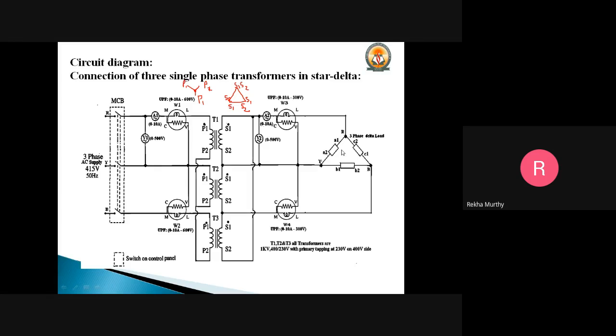For each step we have to take down the readings of all the meters and continue that loading until the transformer supplies the rated power of the respective configuration. Okay, that is how we have to vary this load and note down the readings. Tabulate the columns: primary voltage, primary current, secondary voltage, secondary current, as well as the input power that you have to take down from W1 and W2. We also have to calculate the constants of the wattmeters as we have seen in the previous sessions, and the output power also we have to take down, that is W3 and W4. From this we have to calculate the efficiency and the regulation.